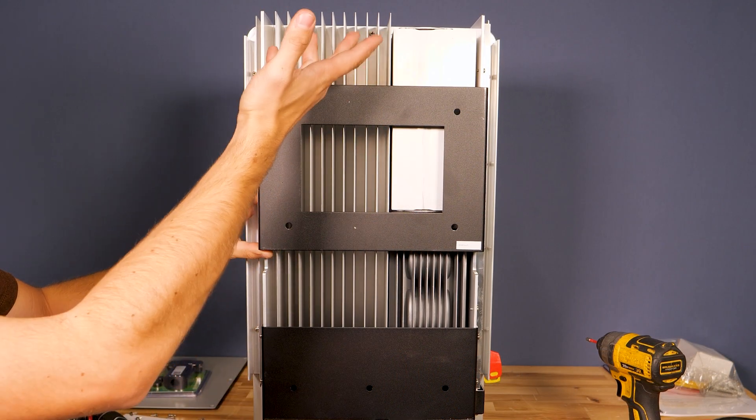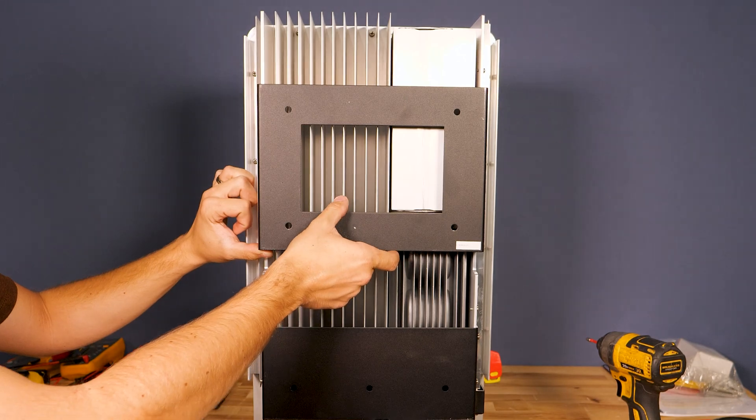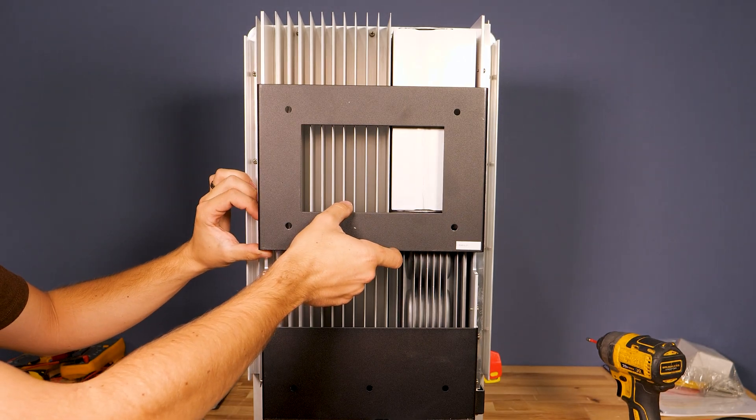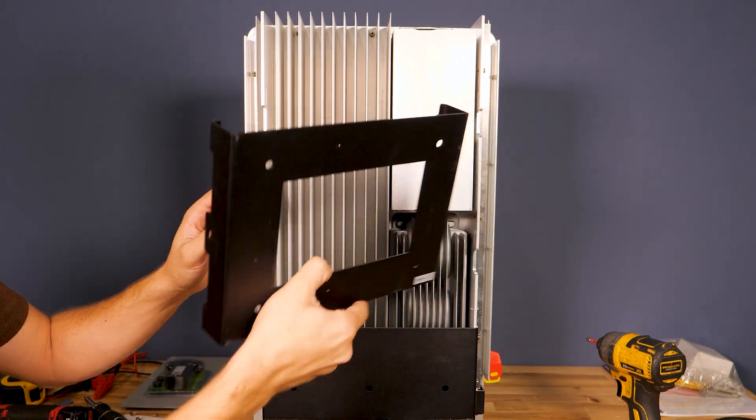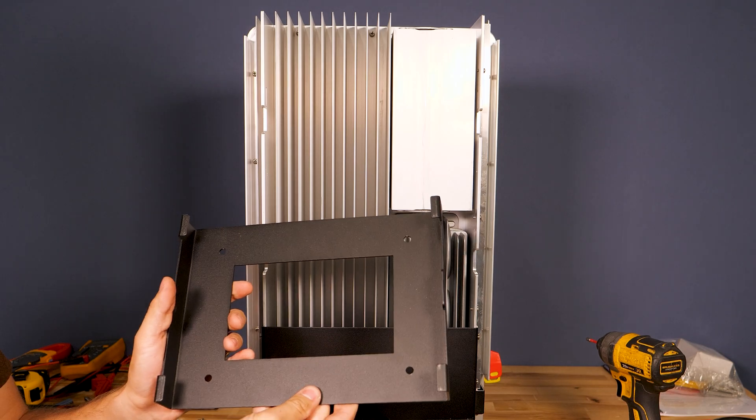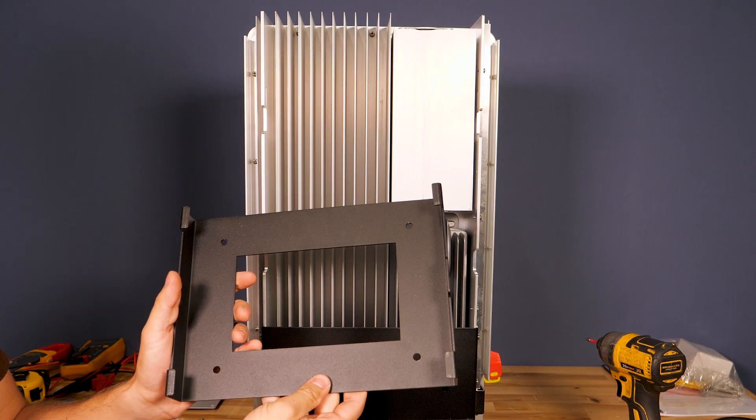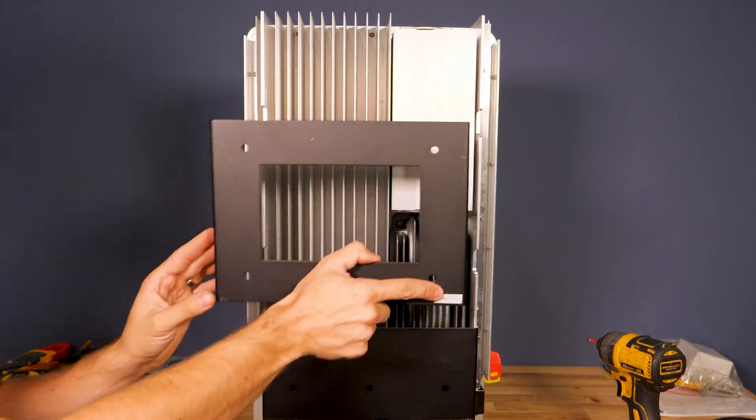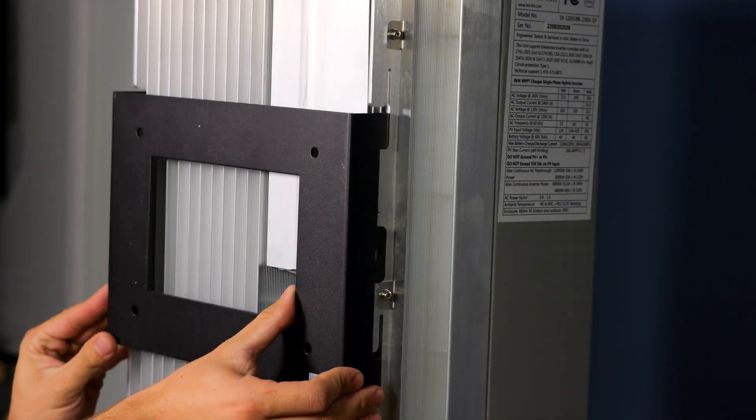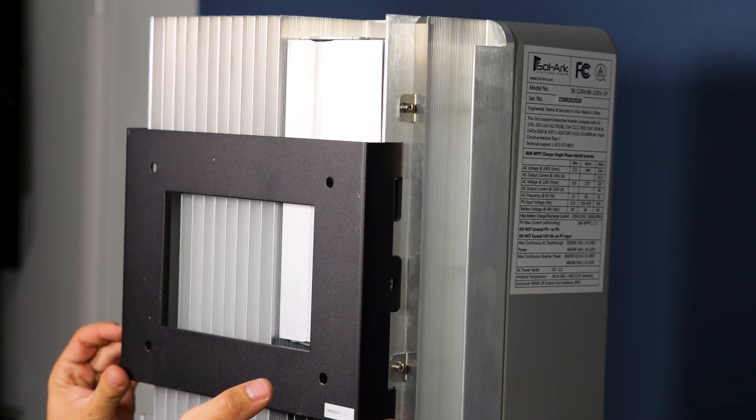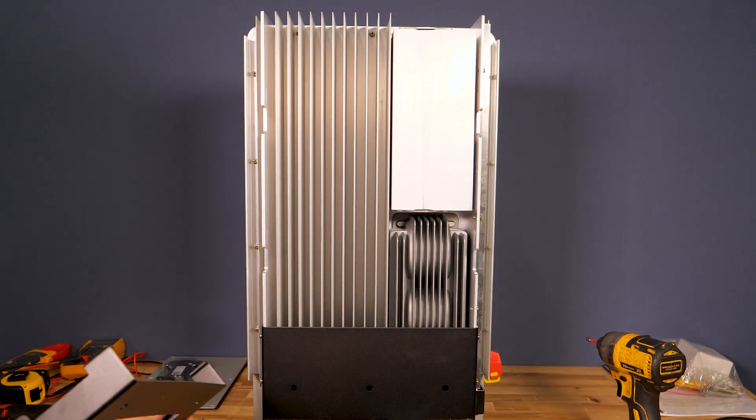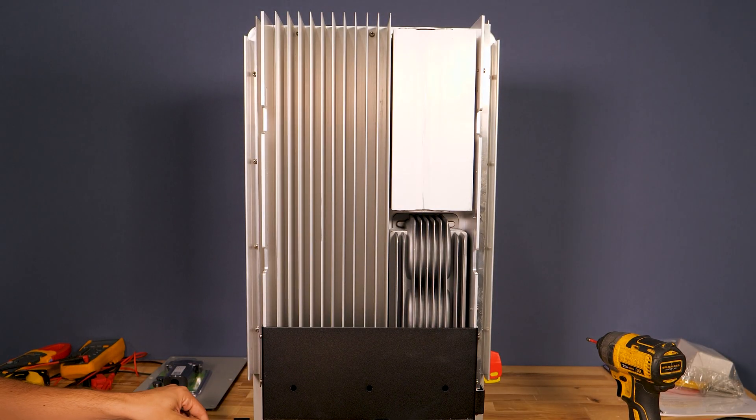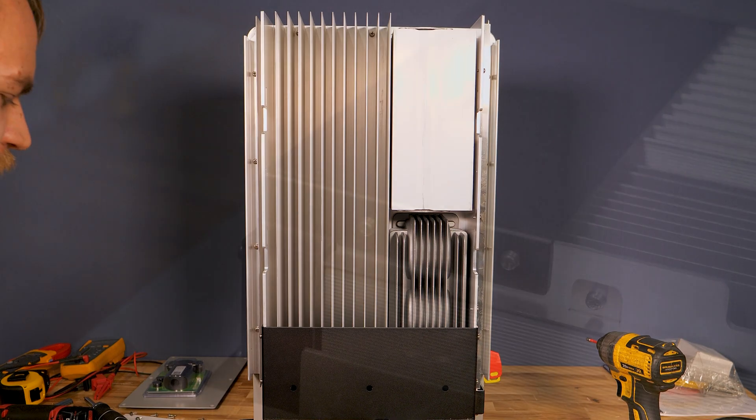This is the back of the inverter. You can see there are quite a few fins for a heat sink and I have removed the screws that lock this mounting bracket in place. You would simply mount this to the wall and then hook the inverter on it and put in the two screws that latch it into place. It's a very easy mounting method and just one person could easily mount this inverter.